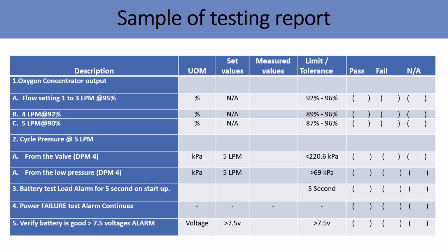And they have a battery test load alarm for 5 seconds. When you power up, the buzzer is going to give an alarm. That's the 5-second alarm. Power failure alarm: when you remove the oxygen concentrator from the plug point, you're going to get an alarm as well. So that's to check the power failure alarm. Inside the oxygen concentrator, normally you're going to see a 9-volt battery. You need to measure that battery with your multimeter to check whether the voltage is above 7.5 volts.